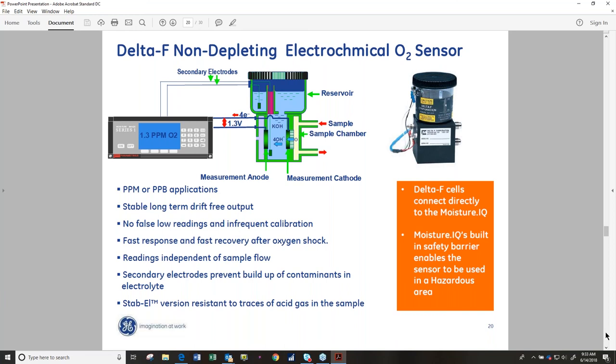And what we've done at GE is we've built in the circuitry to accept the raw signal into our analyzer and also make it intrinsically safe. Our analyzers have a built-in safety barrier, an intrinsic safety barrier to allow you to operate this particular sensor in a hazardous zone. You can also get a variety of different electrolytes. There's one called Stab-El, which has a neutralizer in it. So if you have acid gas, then the Stab-El will neutralize the acid.